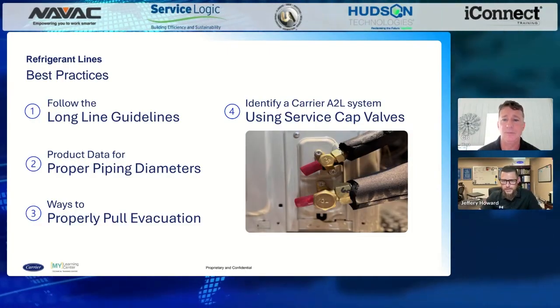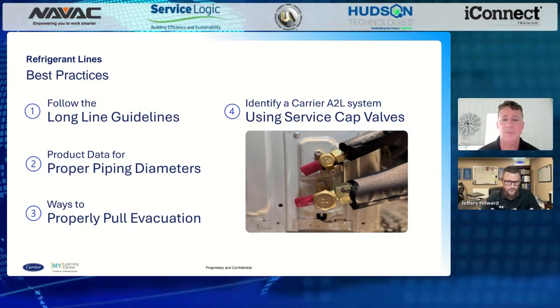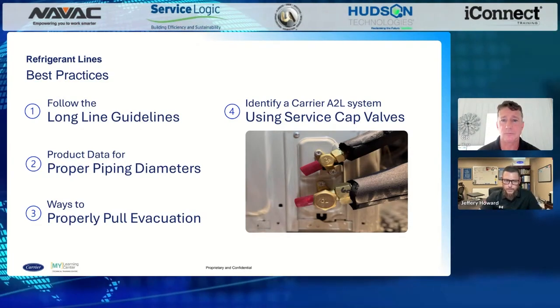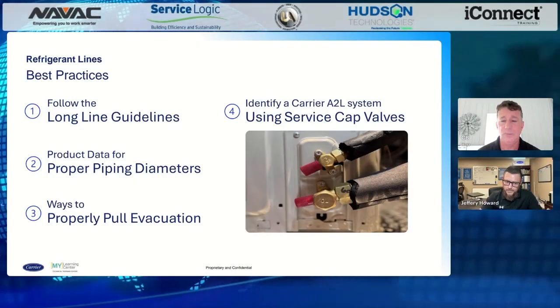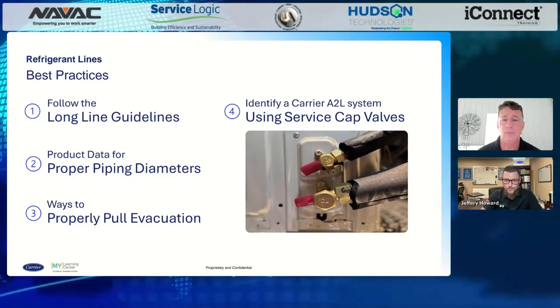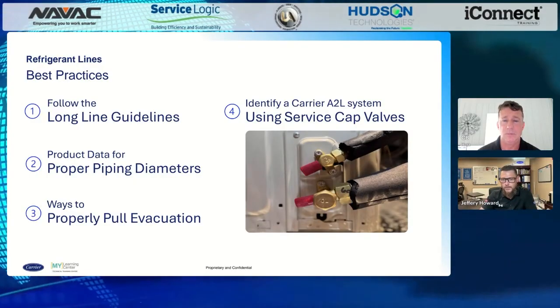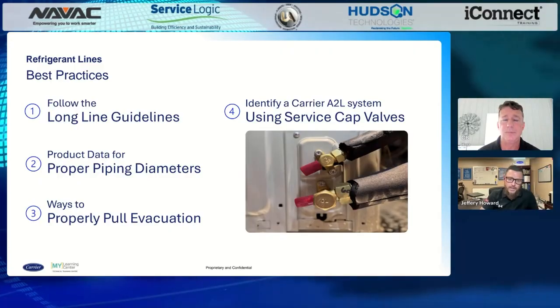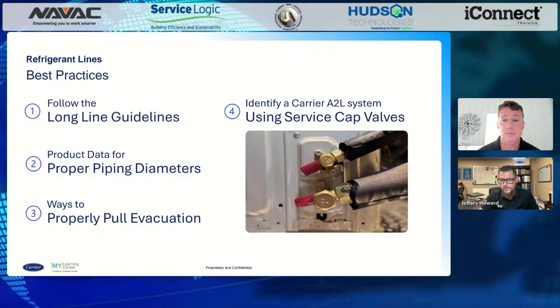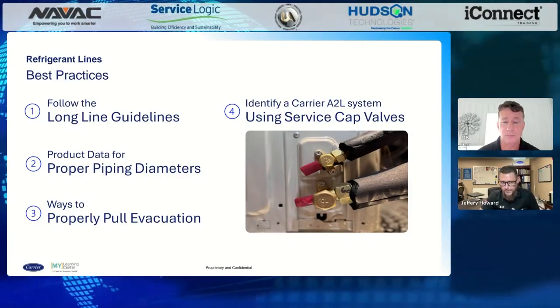And then, of course, you'll want to do a decay test to make sure the system is tight, with no moisture in it. Again, that's part of the dehydration process. Even if you see a climb on a decay test, or don't give it enough time, the system could still be wet. You could still have moisture in it, so make sure you're doing proper decays as well.